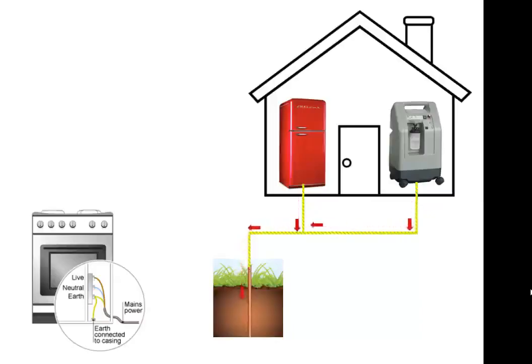If there is not a proper grounding system in place, you would get an electric shock if the phase or neutral wire inside the appliance, such as the fridge, came loose and touched the metal casing. However, if the earth terminal is connected to the metal casing, the current goes through the earth wire instead of causing an electric shock to the user.